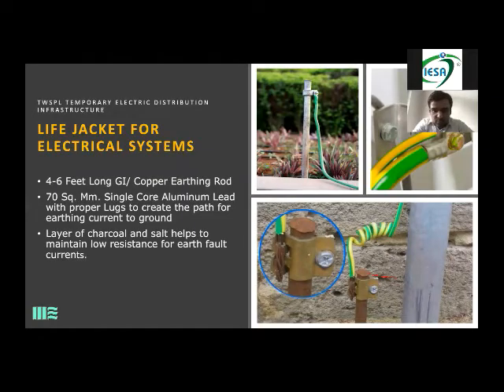But if you're using the right size of cable, as I told you, if a 250 kVA genset can give me only 120 kilowatts, then we are using a 95 square mm copper cable, which as per the rule can take a load up to 250 amps. If you calculate 120 into 1.7, the calculation which I gave you, it will come to around 200. So we are using the right size of cables. When we are loading the cable, we are not putting 250 amps on it, maybe only 200 amps, or maybe only 160. If you travel a distance of 300 meters, there is no power loss. So with the right size of cables, there is no chance that you will get a voltage loss. If you're going to a distance of 500 or 600 meters, that is a separate story altogether. But up to 300 meters, 900 feet, there is no problem.